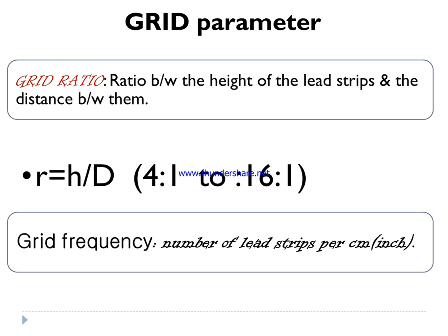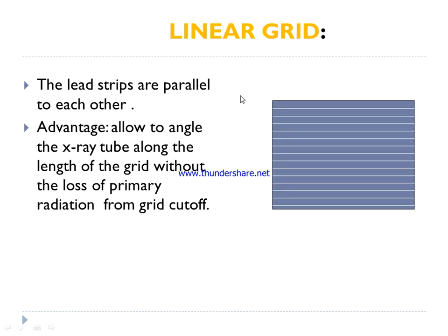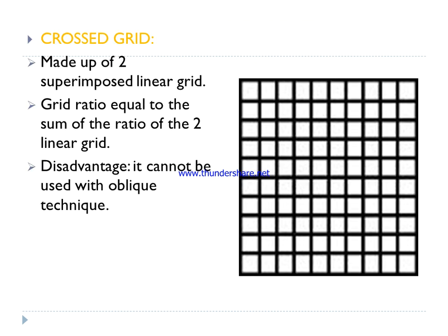The grid ratio ranges from 4:1 to 16:1. Grid frequency is the number of lead strips per centimeter, called grid frequency. There are five types of grids: linear grid, focus grid, moving grid, parallel grid, and cross grid. In a linear grid, the lead strips are arranged parallel to each other in a linear fashion. They allow angulation of the x-ray tube along the length of the grid without grid cutoff loss of primary radiation.